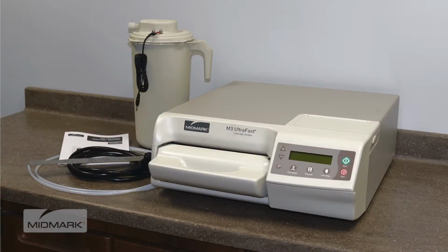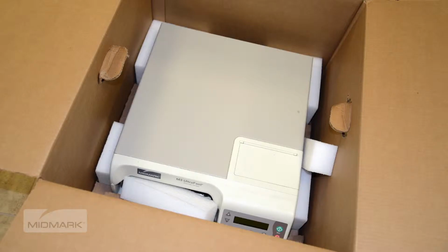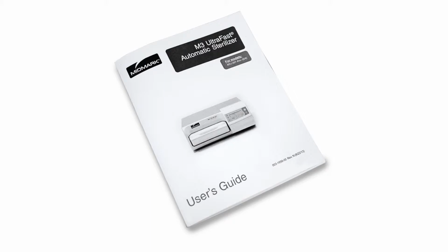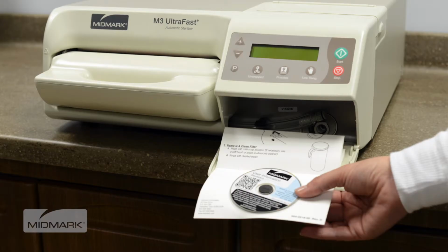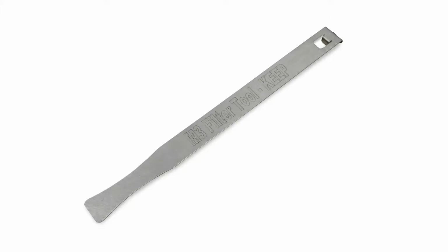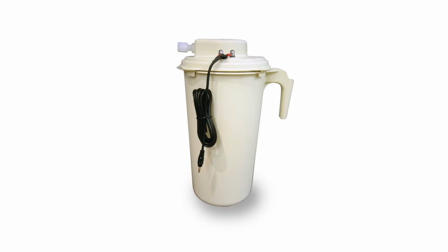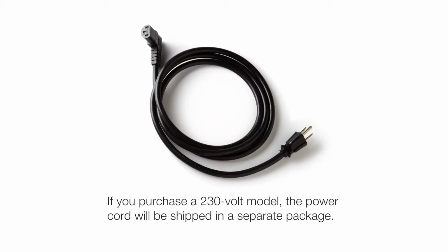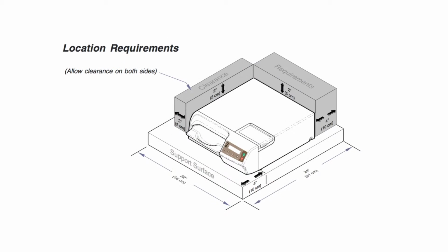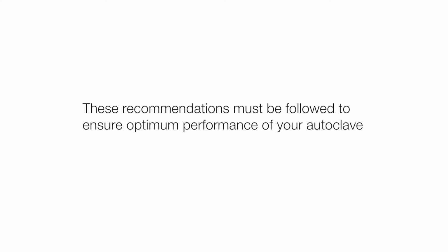Included with the M3 Ultrafast automatic sterilizer purchase, you will find the M3 Ultrafast unit, M3 User's Guide, Quick Reference Guide and User Training CD, filter change tool, drain hose, external condensing tank and tubing, and a power cord. This illustration can be found in the M3 User's Guide. It provides critical information for installing the M3 Ultrafast, including required clearances around the unit. These recommendations must be followed to ensure optimum performance of your autoclave.